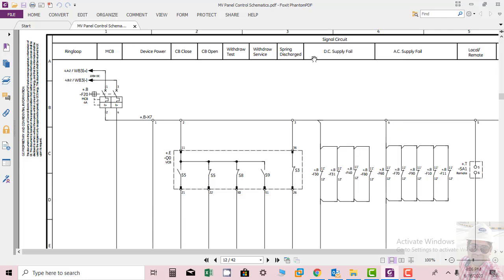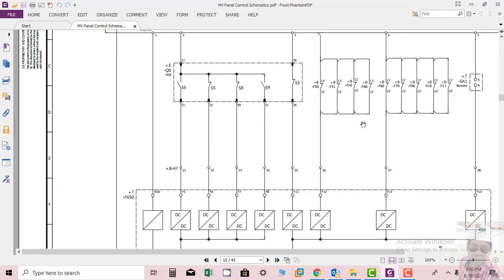You can see if any of the circuit breakers is off. Now all the circuit breakers normally shown in the drawing are in off position, so normally it will be on. So this all contact will be open. As soon as any of the MCB trips, then contact will close, and this will energize the binary input, and this in the alarm and indication can be configured at the control room or automation systems at remote control rooms.